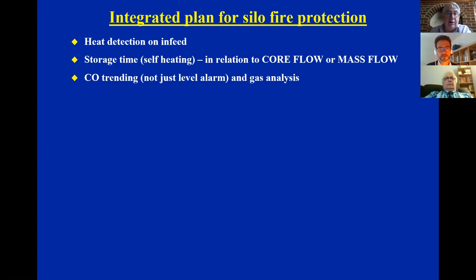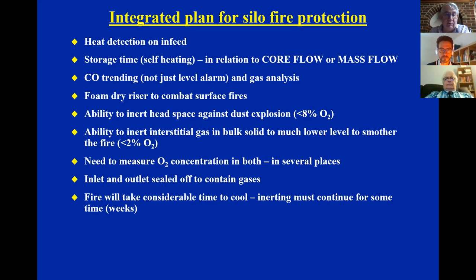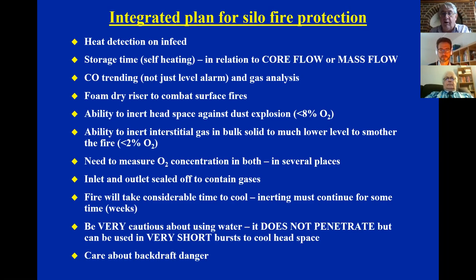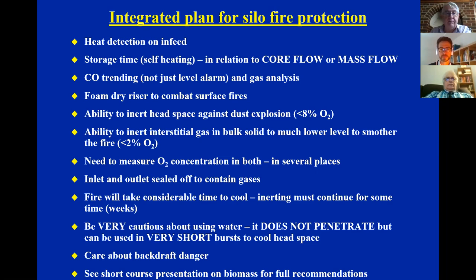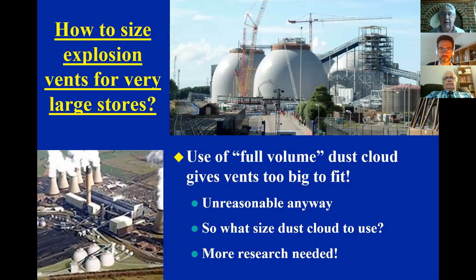At the Wolfson Center we've developed an integrated plan for silo fire protection covering multiple points — if you install all of these on your silo, you have a very good chance of preventing and dealing with fires; any missing and a fire can run away from you. For explosion vents on large stores — the big domes at Drax Power Station, where we had heavy involvement — if you size explosion vents assuming the whole dome is filled with a dust cloud at explosive concentration, there is not enough surface area for all the vents required. We therefore work with a reduced-volume dust cloud, which brings the interesting challenge of determining how large that cloud should be.